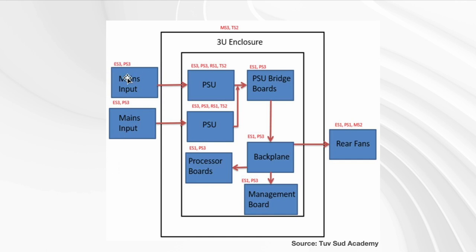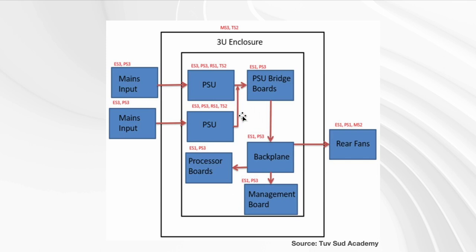Looking at energy sources: mains input is always ES3, and then it goes down — ES1, ES1, ES1. A rear fan, however, is a mechanical source at MS2 because there are some moving parts. That's outside the scope of this training. At least you really clarify what is ES3, ES2, and ES1, and based on that you can plan for your safeguards.